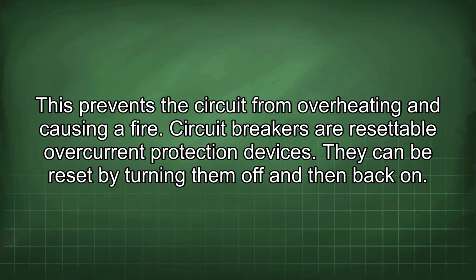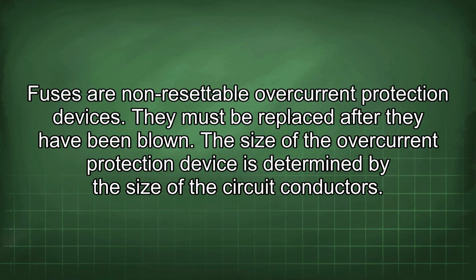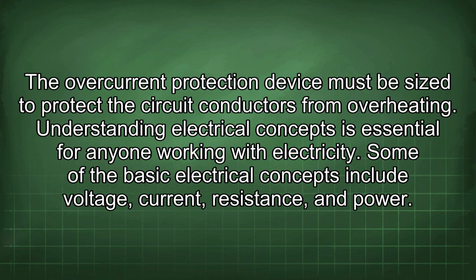Circuit breakers are resettable overcurrent protection devices. They can be reset by turning them off and then back on. Fuses are non-resettable overcurrent protection devices. They must be replaced after they have been blown. The size of the overcurrent protection device is determined by the size of the circuit conductors. The overcurrent protection device must be sized to protect the circuit conductors from overheating. Understanding electrical concepts is essential for anyone working with electricity. Some of the basic electrical concepts include voltage, current, resistance, and power.